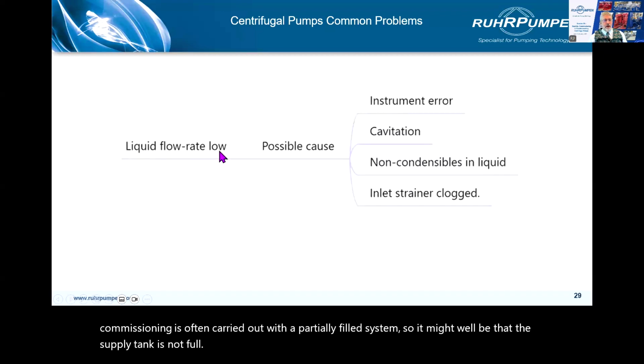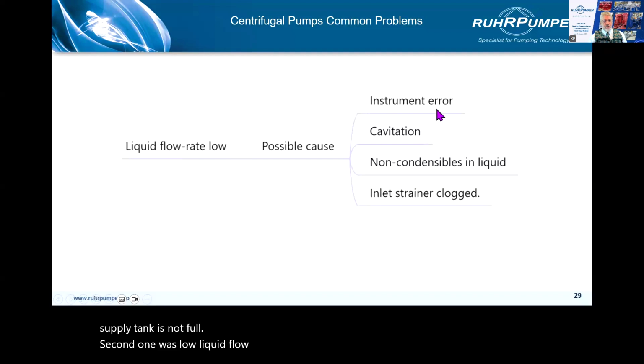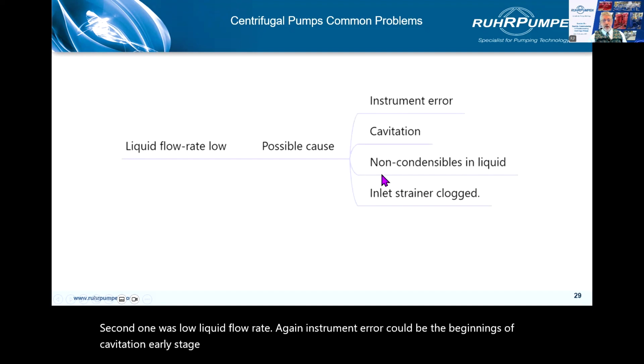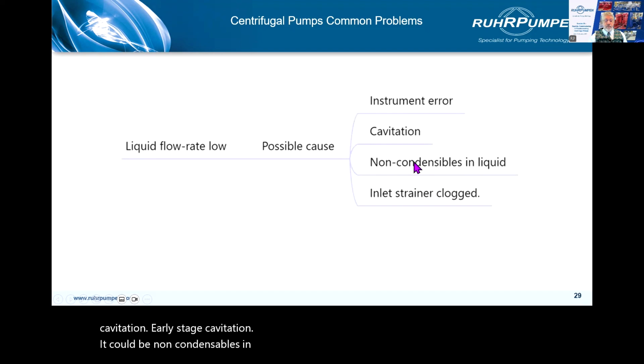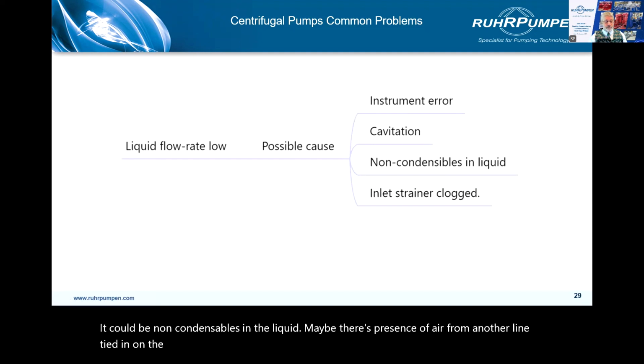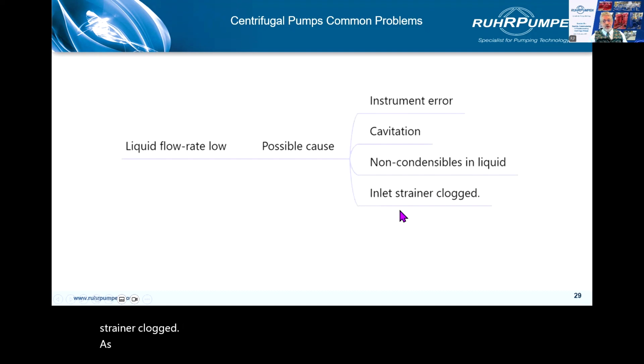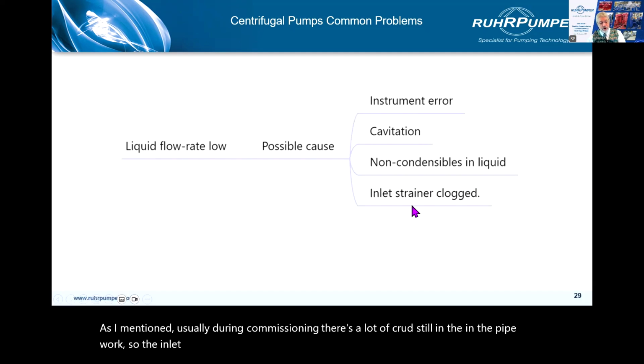Second one was low liquid flow rate. Again, instrument error, could be the beginnings of cavitation, early stage cavitation. There could be non-condensables in the liquid. Maybe there's presence of air from another line tied in on the suction side of the pump. And here's a common one on commissioning, inlet strainer clogged. As I mentioned, usually during commissioning, there's a lot of crud still in the pipework, so the inlet strainer might well be clogged.